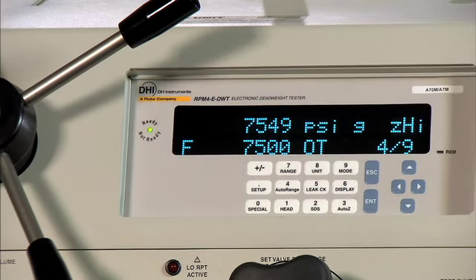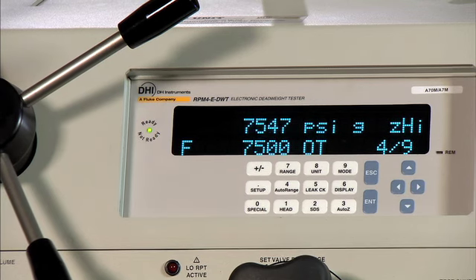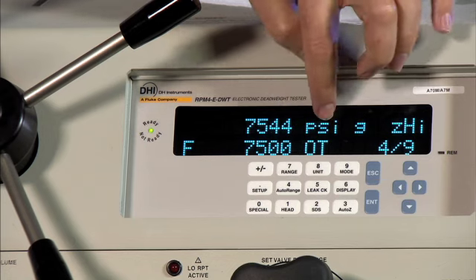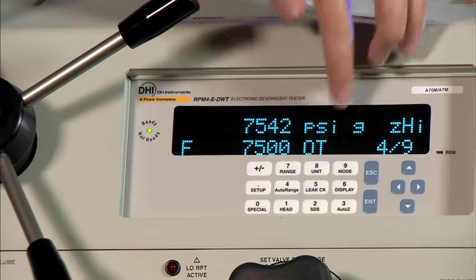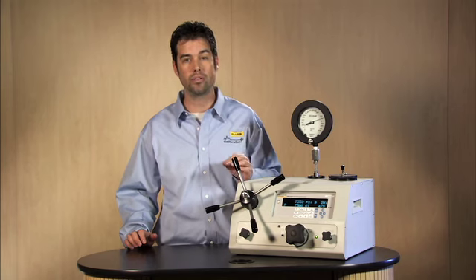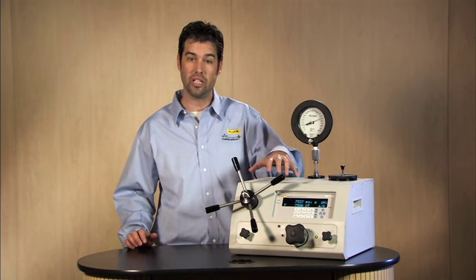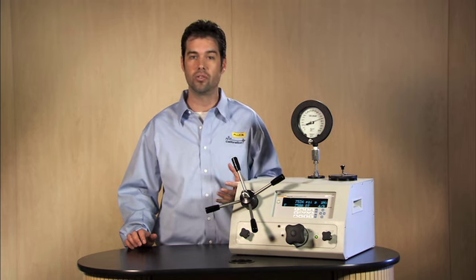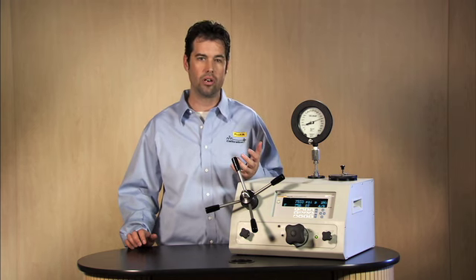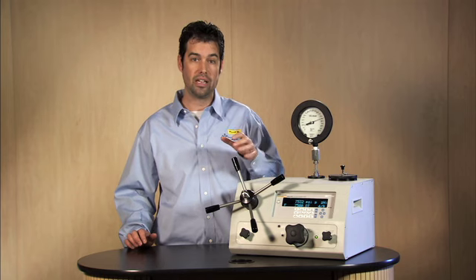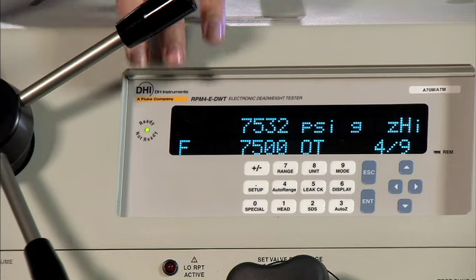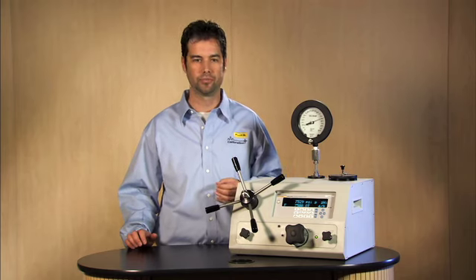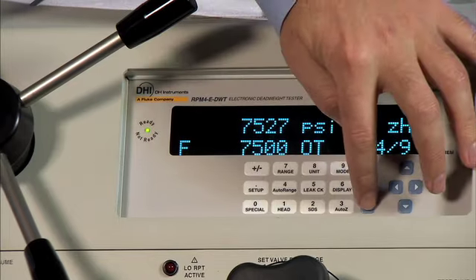That value, that tone that you just heard, is the tone that says out of tolerance. And it also indicates OT, out of tolerance. Every single one of these points, in tolerance or out of tolerance, is being logged internally on the RPM4, where you can retrieve these values either via a computer or you can go back on the main run screen and observe what those values are. You can store up to 10 files. So push enter to acknowledge it.